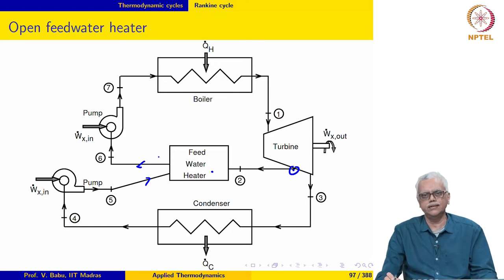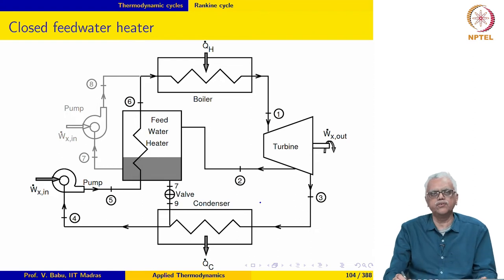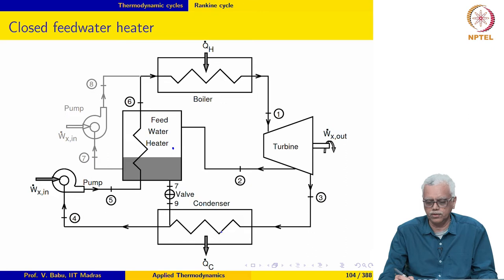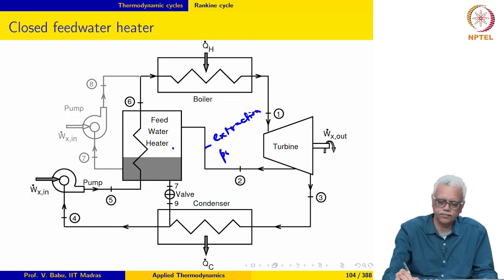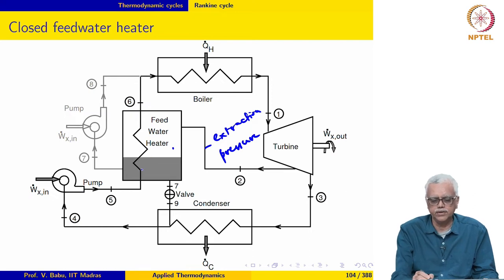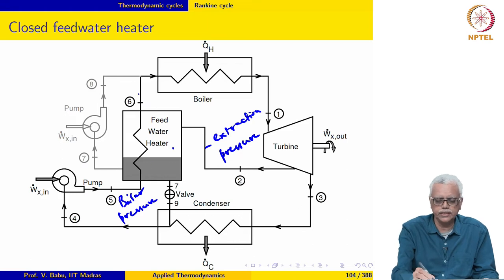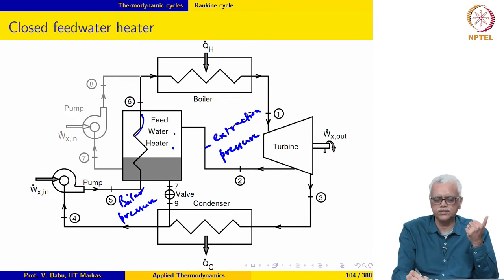This is a requirement because all the streams are being mixed physically in the feed water heater. In contrast, in a closed feed water heater, the pressure of the different streams can be different from each other. As before, part of the steam is extracted from the turbine at extraction pressure. The feed water that enters the feed water heater is at the boiler pressure, not the extraction pressure. It goes through a separate path and never mixes with the steam extracted from the turbine, so it can be at a different pressure.